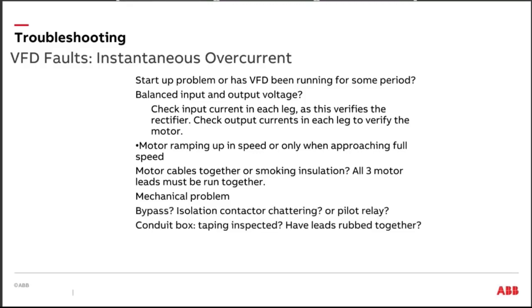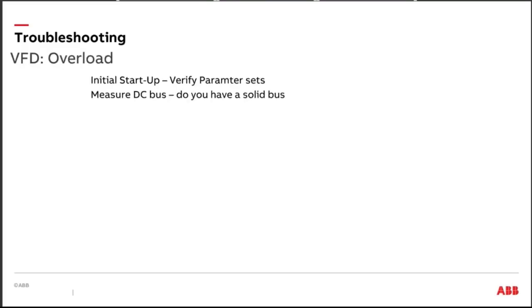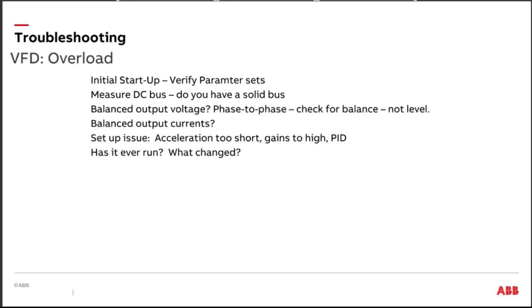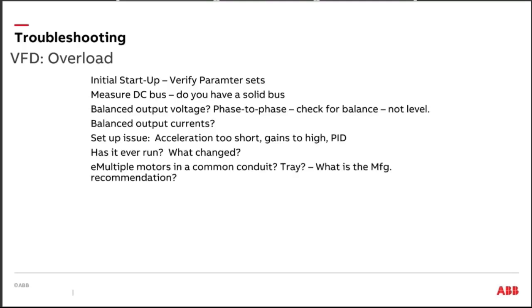Again, is your bypass, and is that output contactor chattering there? Okay, is the motor in a wet application or wet installation, something along those lines. Overload on startup. Let's look at the drive. Let's look at the setup and make sure that the drive has been set up right. Who commissioned the drives? Do you know this person? Do you know that they've done a good job? Did they do the tune? Is everything done correctly? Did you measure your DC bus? Do you have a nice solid DC bus on this drive? Okay. Are your outputs balanced? Okay. Are you trying to accelerate a load up too fast?